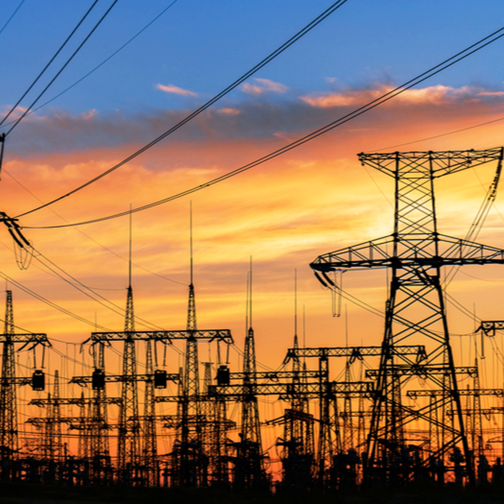But the air doesn't always have the same resistance. What about humid or foggy days? You've touched on a constant battle engineers fight, corona discharge. On humid days, or especially around high voltage hardware, you might hear that sound, a faint sizzling static. That's corona loss. It's the sound of the incredibly strong electric field at the surface of the wire, literally ripping electrons off of air molecules, ionizing them and creating a tiny glowing plasma.